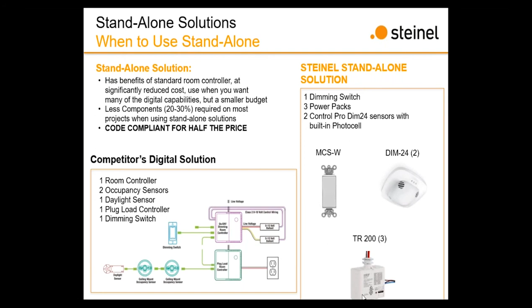Yeah, absolutely. Commissioning is extremely simple. We have the light level settings right in the app, and believe it or not, it's that picture right here where we set that setting. As you know, the light seen by that closed loop photocell, along with the 0 to 10 volt wires on that dimming sensor, will adjust the lights based on the settings we input on our IR remote. It is adjustable, and since the app is free, we can adjust it at any time. Very easy commissioning, very easy setup.